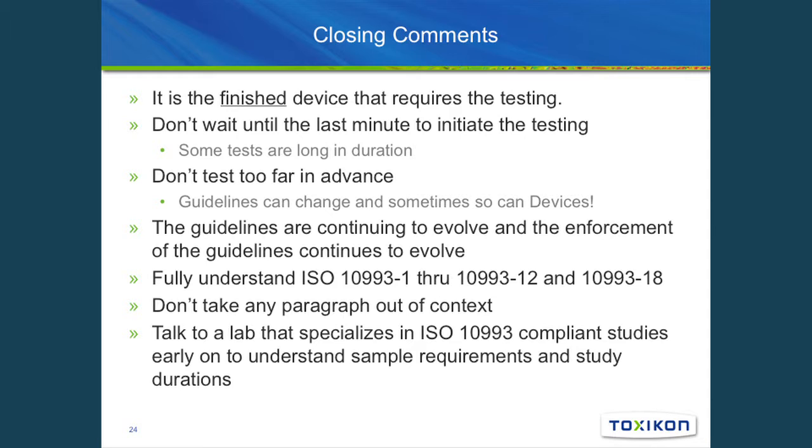If you go too far in advance, there are things that can happen. Guidelines change, and how you do something can change. The regulatory body you're going to be submitting to may have a couple of changes. Devices actually change, with design freezes. If you haven't gotten to a design freeze, be careful about jumping into your full biocompatibility.